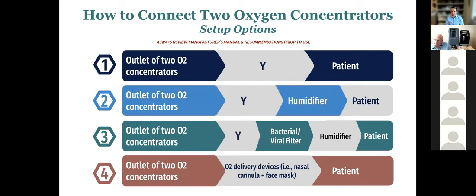If you have access to bacterial viral filters, inserting that and or a check valve before the humidifier can keep the equipment between that and the concentrator clean. So that is another way to do this. And another way would just be simply to take two concentrators, connect each of them to a delivery device, and put both of those delivery devices on the patient. So for example, one concentrator may be connected to a nasal cannula, the other concentrator to a simple face mask, and both placed onto the same patient.